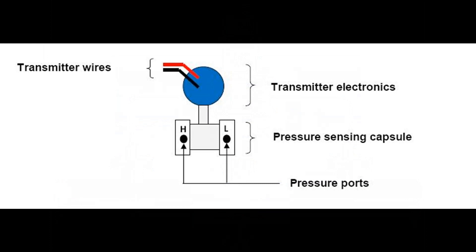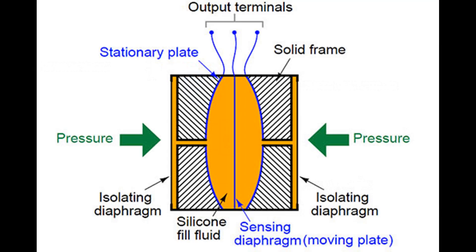A DP transmitter typically employs two pressure sensors, one for each pressure port. These sensors are commonly referred to as the high side and the low side pressure sensors. The high side pressure sensor is connected to the port on the high pressure side of the primary element, upstream.